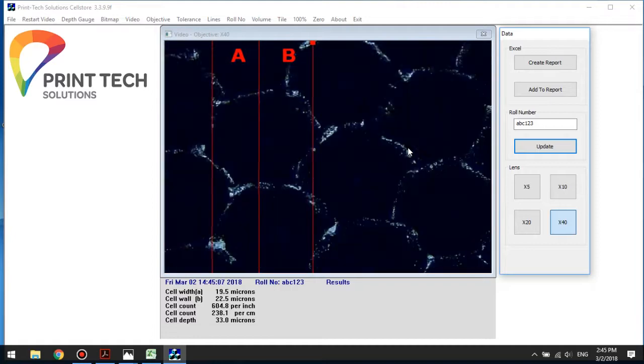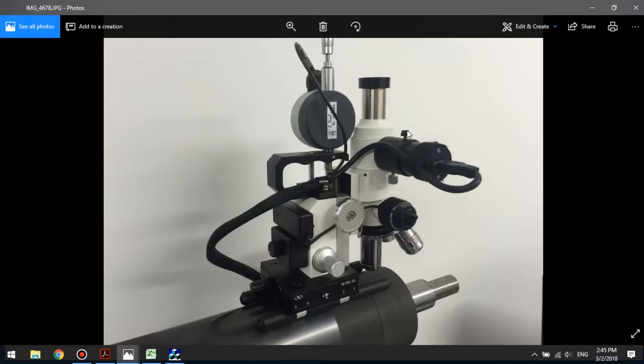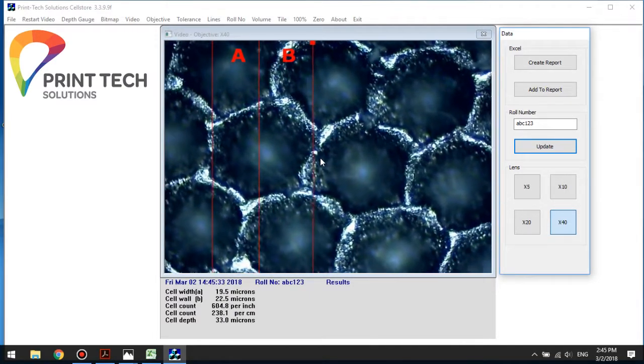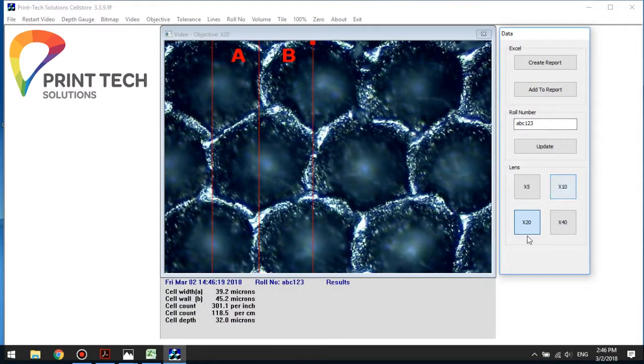There we have our cells. The next thing I need to do is align the cells so they correspond with the cursor so that I can take my measurements. I'm going to do this by rotating the camera — if I loosen that screw, I can rotate the camera and that will allow me to square the cells to the cursor. Now that I've got my image, I need to check that the lens selection in the software corresponds with the lens in the microscope. The microscope has three lenses mounted in the nosepiece and one additional. I'm using the x20 for this demonstration, so I've selected x20, which will tie in our calibration and give us our correct results.